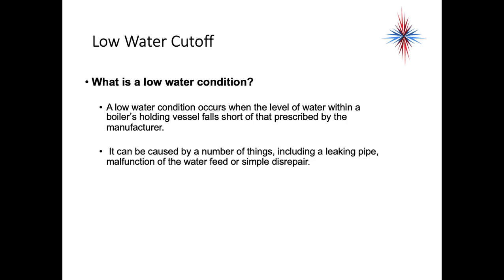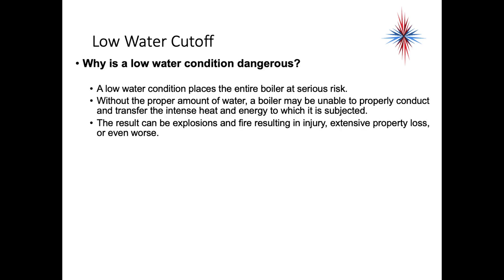So what is a low water condition? A low water condition occurs when the level of water within the boiler falls short of a pre-described level set by the manufacturer. It can be caused by a number of things including a leaking pipe, malfunction of the water feed, or simply disrepair of a system. Regardless of the cause, we cannot operate a boiler if the water level is below a certain point in the system.